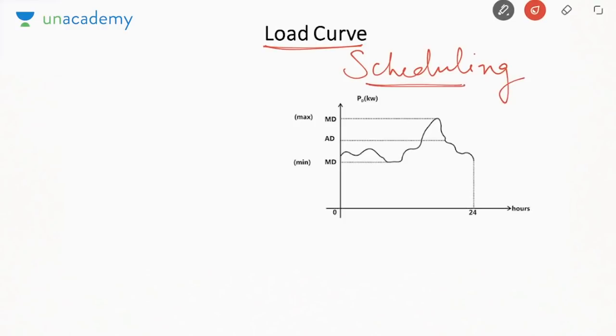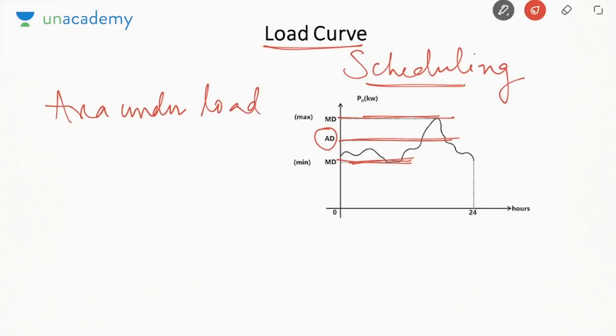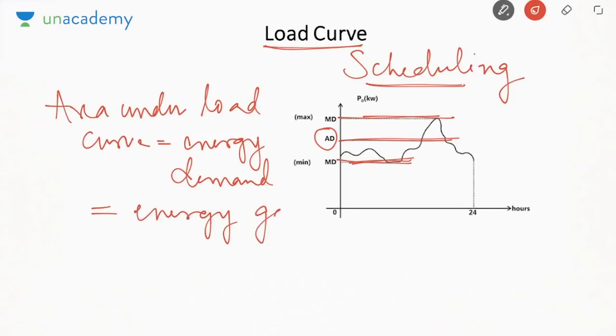Okay. So from load curve we can see there are three parameters that we have defined. AD means average demand. This means maximum demand and this means minimum demand. From the load curve we can determine three things: average, maximum and the minimum demand. And area under the load curve, so integration of power with respect to time gives us energy, energy demand, and usually if we neglect the losses, this will be equal to energy generated. So these are the how many units need to be generated in an entire day or a year. If this is plotted from 0 to 24 hours, it is called as a daily load curve.